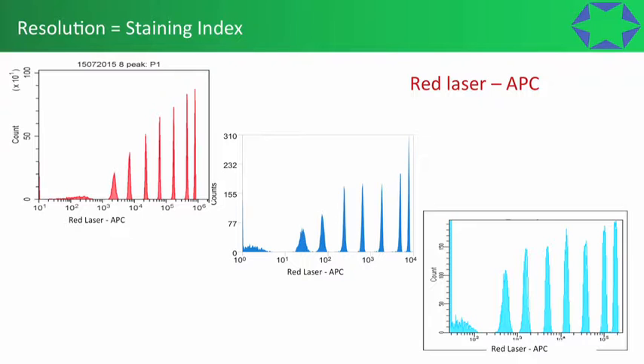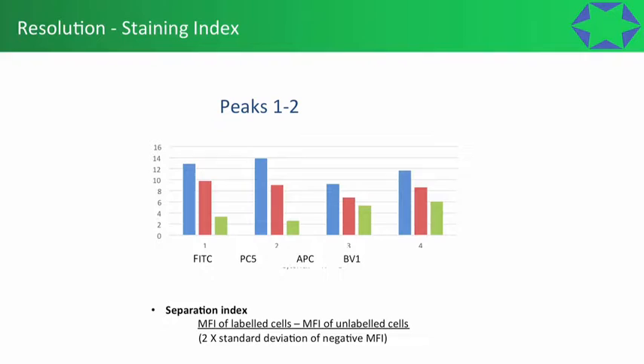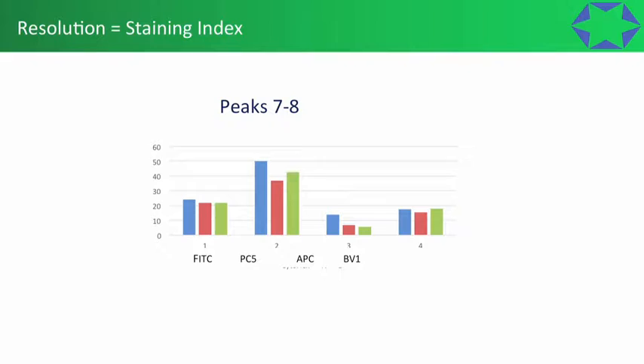Looking at the 640 laser, all peaks are present in the APC channel on all instruments. But as we go out into the far red, again we see some advantages with the CytoFLEX over the other two instruments. Crunching the data through and looking at the staining index, the blue bars show the CytoFLEX with an increased staining index for peaks 1 and 2. There is a particular advantage in the PE-Cy5 and APC far-red shifted channels with the CytoFLEX, and this will be echoed throughout the whole presentation.